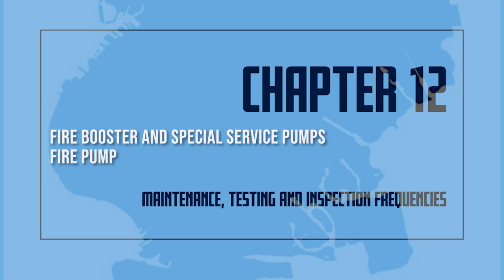Fire pump. Weekly visual inspections shall be made to ensure that the pump suction and discharge and the bypass valves are fully open, all piping is free of leaks, suction line pressure gauge readings are normal and that the reservoir is full. System line pressure gauge readings are normal and that the wet pit suction screens are unobstructed and in place.